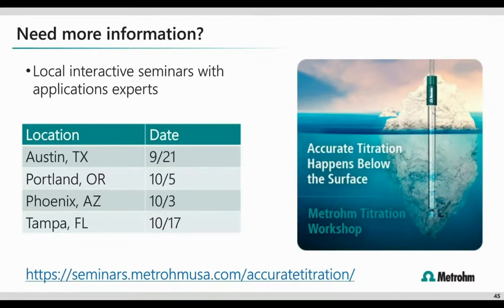Excellent, thank you. Now our next question asks, would it be better to warm or cool buffers to a similar temperature as the sample, or warm the electrode in the sample and use room temperature buffers? Can you repeat that question for me? Sure. Would it be better to warm or cool buffers to a similar temperature as the sample, or warm the electrode in the sample and use room temperature buffers? Okay, so when it comes to temperature, we want to measure the buffers at room temperature. We don't want to heat anything, either the electrodes or the buffers. With your buffers, there will be a calibration table or buffer table with temperatures, so we need to tell the system what temperature we plan to perform the calibrations at.